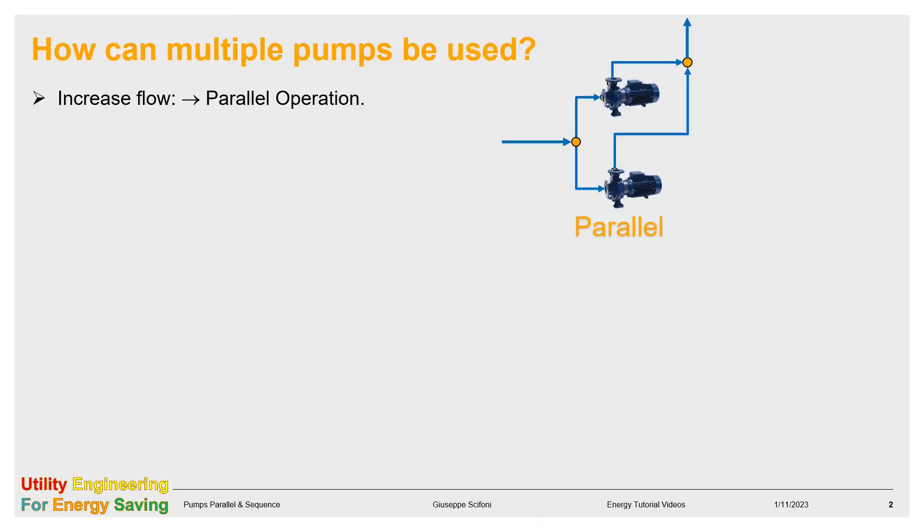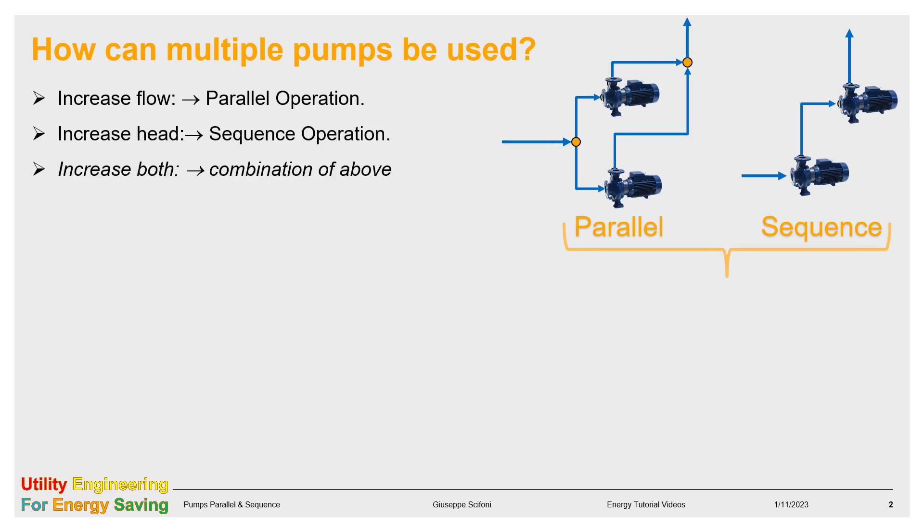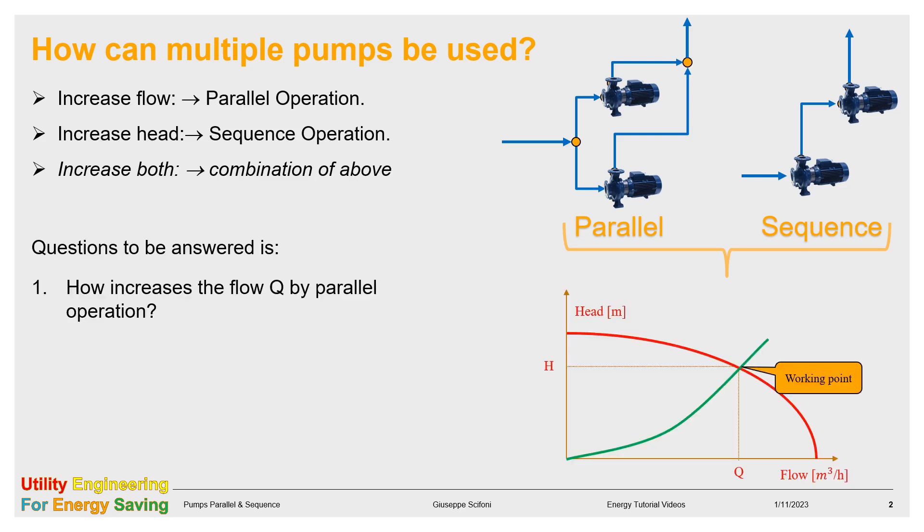The reason why multiple pumps are used is for increasing the supply capacity of the system. To increase the flow, the pumps must be in parallel. To increase the head, they must be in sequence. To increase both, we need a combination of above. In any case, the working point, defined by H and Q, is the intersection between the pump curve, the red one, and the load curve, the green one.